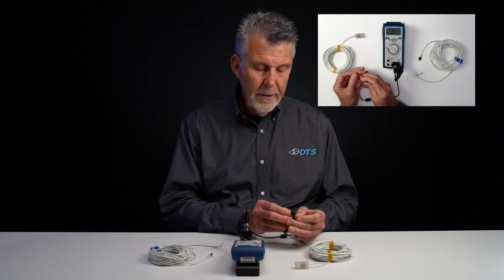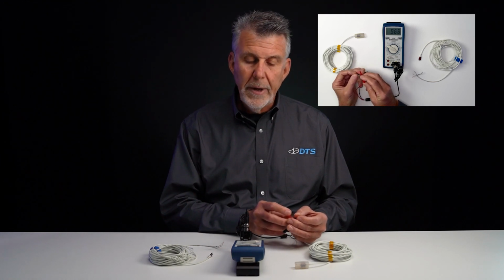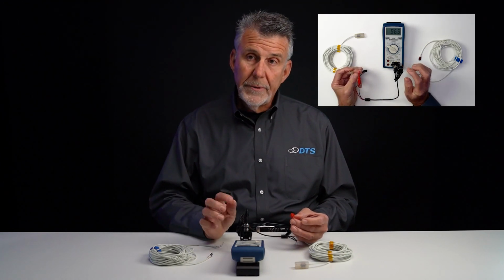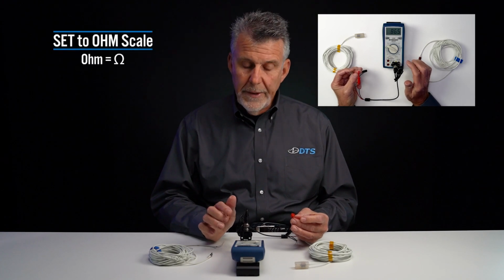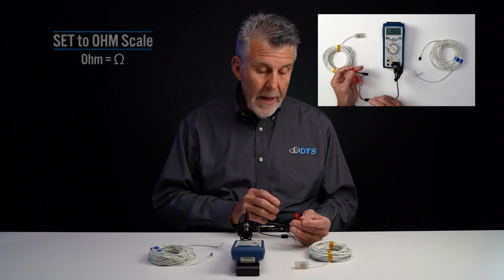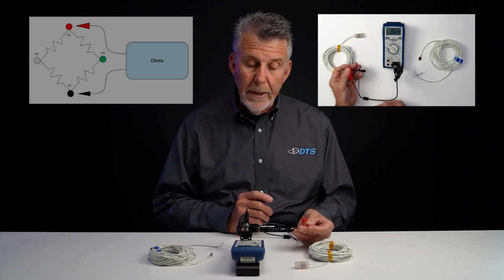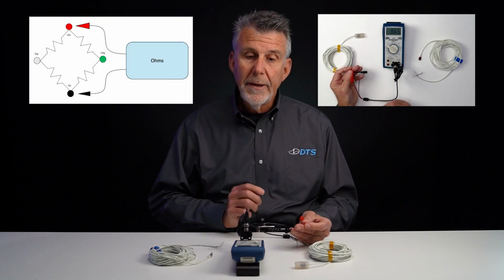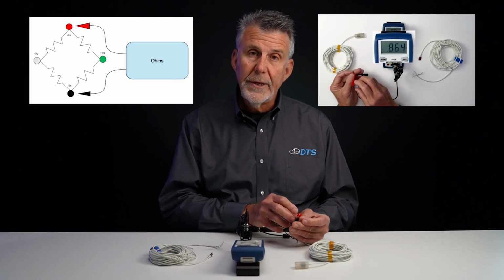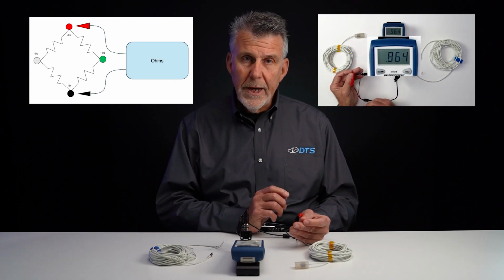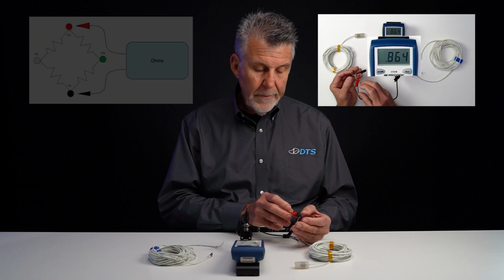The first thing I'm going to do is connect my multimeter set to the ohm scale, in this case 2000 ohms full scale, and I'm going to see what resistance I get between the plus and minus excitation. And I'm seeing 864 ohms. This is pretty typical for this type of sensor.